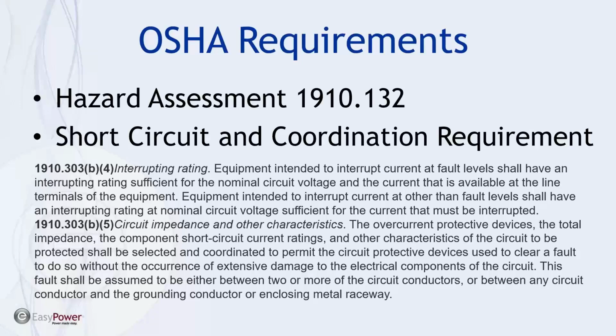So this is one of the reasons why we're getting so many arc flash incidents every year, is because people have done their arc flash studies once and never again. Let's take a plant that came into existence in 1964. They knew what kind of load they were going to have based on the equipment that they were installing, so they sized up the transformer, sized up the main switchgear, and all the panels for the facility. They went by the load for overcurrent protection, and then they did an assessment based on the transformer and the available fault current from the utility. They made an assessment of what their fault current was so they could do a short circuit and coordination study of the plant, which is required upon completion.